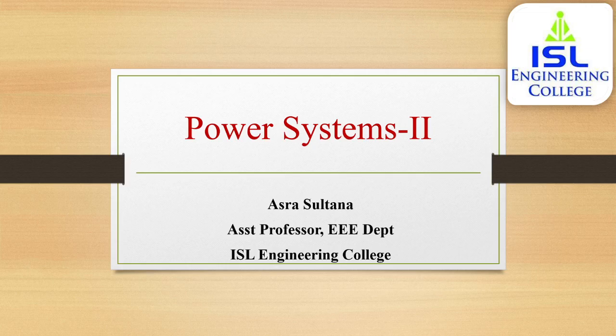And we have seen a very important topic called percentage reactance and base kVA. Percentage reactance of an equipment depends upon its kVA rating. Generally, various equipments used in the power system have different kVA ratings. Therefore, it is necessary to find the percentage reactances of all the elements on a common kVA rating. This common kVA rating is known as base kVA. The value of this base kVA is quite unimportant and it can be equal to that of the largest plant or equal to the total plant capacity or any arbitrary value.